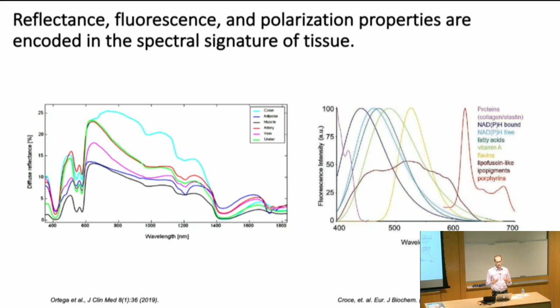And you can do this with various methods of scanning. You can either get it point by point. In this case, it literally is just doing spectroscopy for each point. You can collect for a full line and then collect the data with a 2-dimensional detector and scan line by line. You could scan through wavelength using something like a tunable filter or a filter wheel. And then they have these really fancy systems called snapshot systems, but in my experience, these tend to not be super robust. So usually you'll find it's a scanning method.